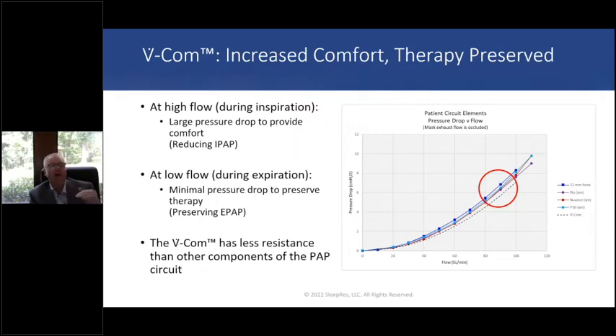We'll just leave you with that. We filed a bunch of patents this year. The large flow creates a large pressure drop and comfort during inspiration. During expiration, there's low flow, and therefore minimal pressure drop. So you don't drop EPAP, you preserve therapy, and you preserve the exhaust, protecting against rebreathing.